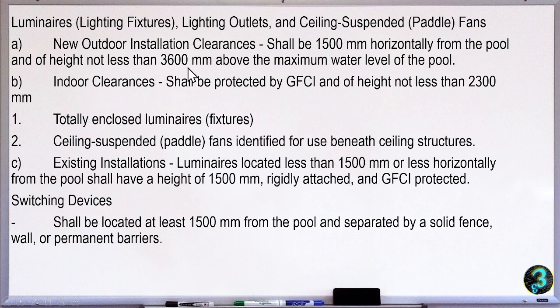less than 3,600 mm. Indoor clearance cells shall be protected by GFCI and a height of not less than 2,300 mm. So, these are the following na dapat, ito yung susundin na standard. May GFCI, tapos hindi bababa ng 2,300 mm ang height. Totally enclosed luminaires, ceiling suspended paddle fans, identified for use beneath ceiling structures. Tapos, yung mga existing installation located less than 1500 mm or less horizontally from the pool and shall have a height of 1500 mm. Tapos, rigidly attached at naka-GFCI.